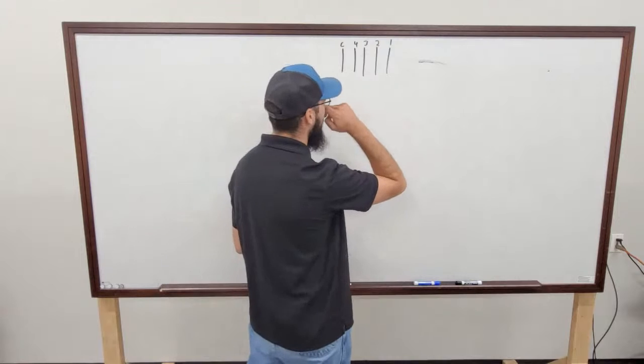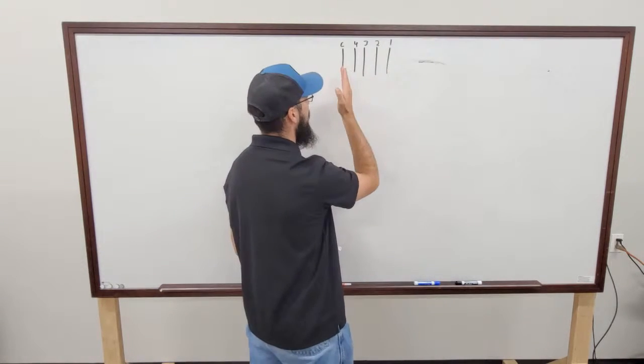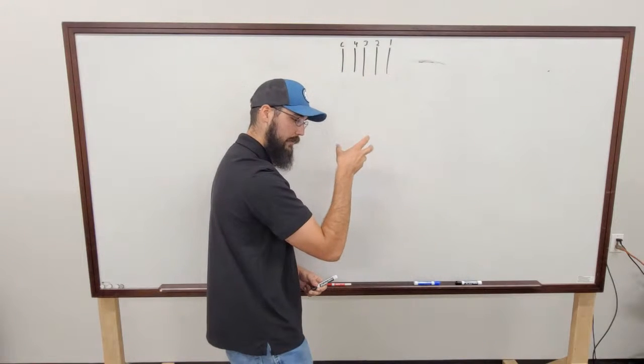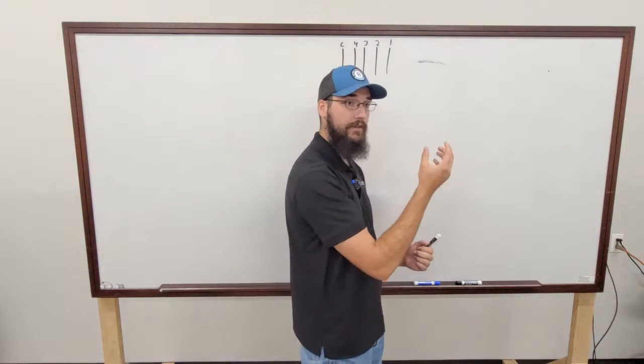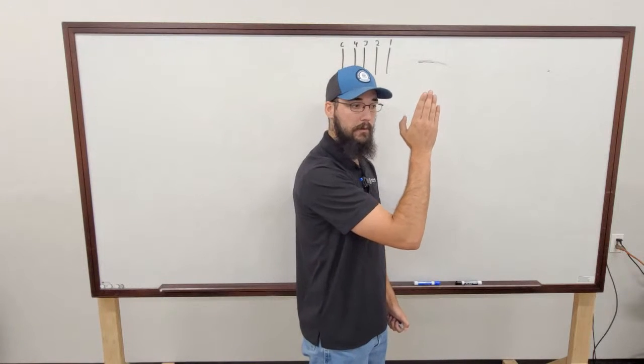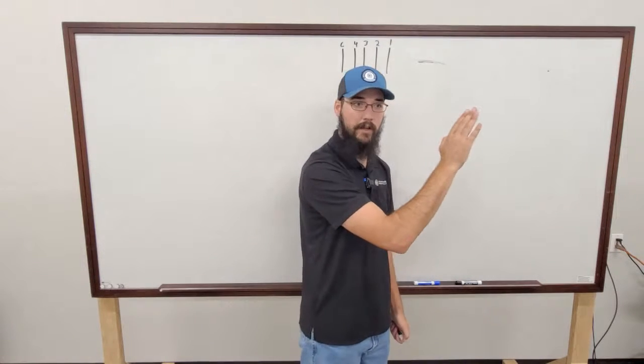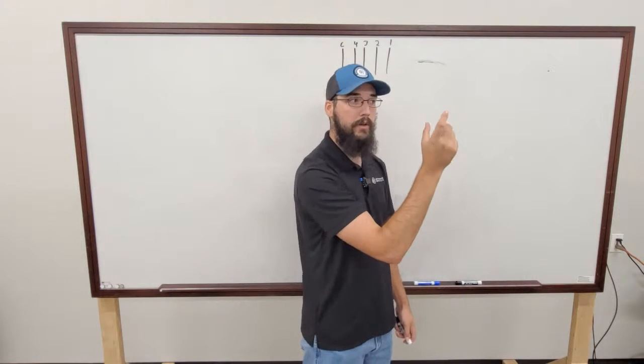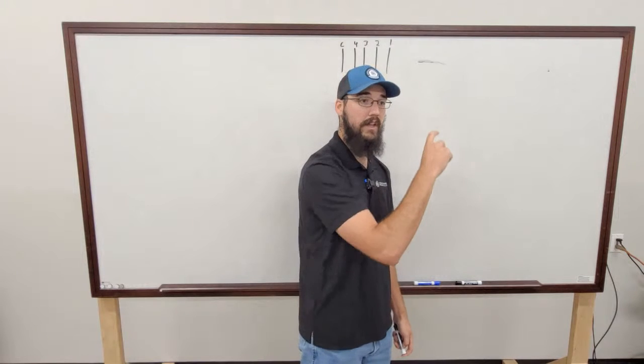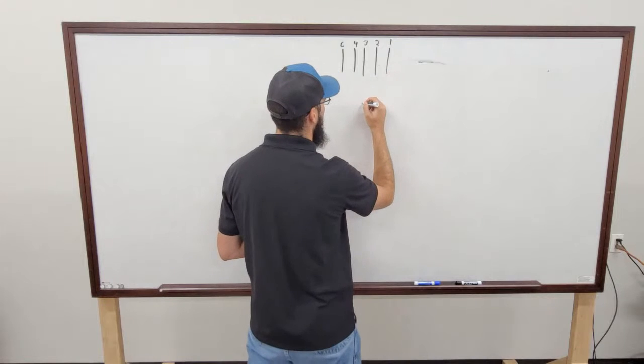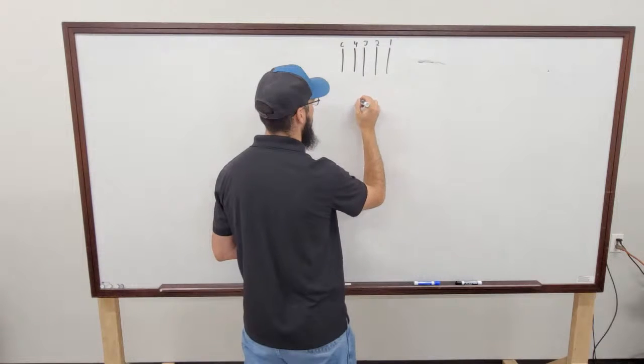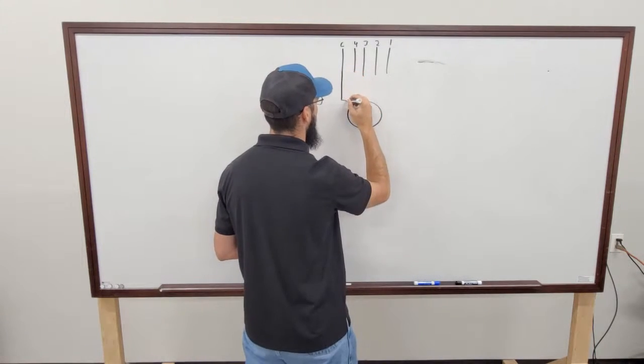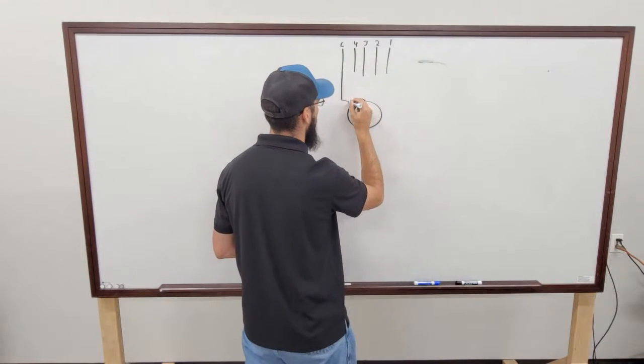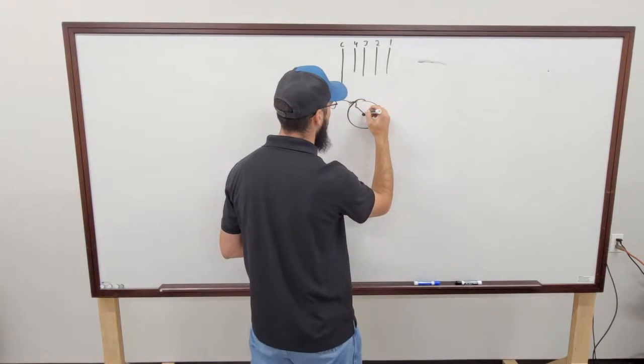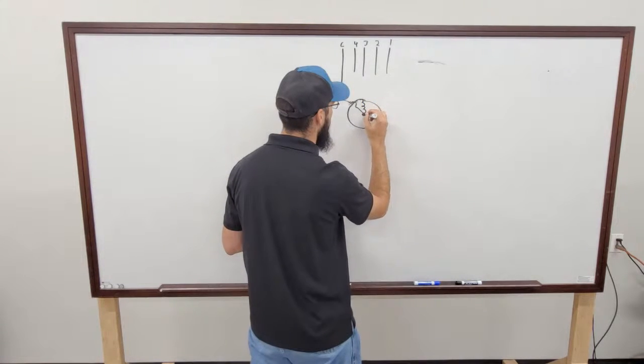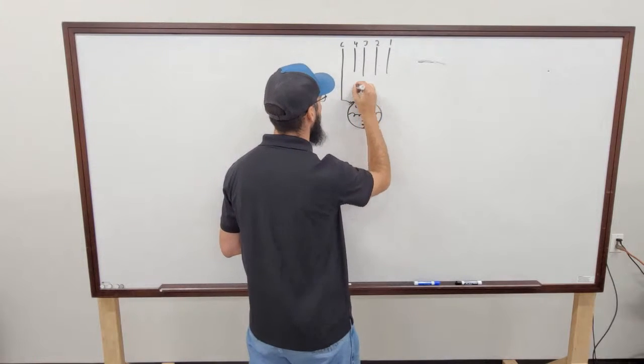So there's two primary lines of thought. Inside the EXV motor head, it's a motor driving a shaft on a threaded bolt. You will have multiple windings. They're just little bitty tiny windings that trigger, and depending on how we reverse polarity through those windings decides how we step. So, for example, this common would feed to a common point in the center, and then you would have 4 different internal windings, each of these feeding each one of these legs.